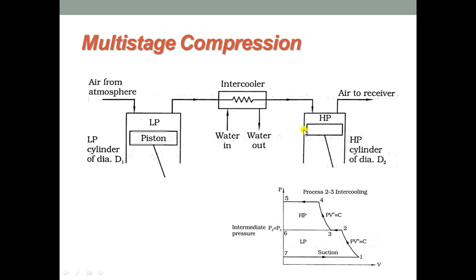In case it is desired to increase the compression ratio of the compressor, then multi-stage compression becomes inevitable. If you look at the expression for volumetric efficiency, it shows that volumetric efficiency decreases with increase in pressure ratio. This aspect can also be explained using PV representation shown in figure. Therefore, the volumetric efficiency decreases with increase in pressure ratio in compressors with single stage compression.